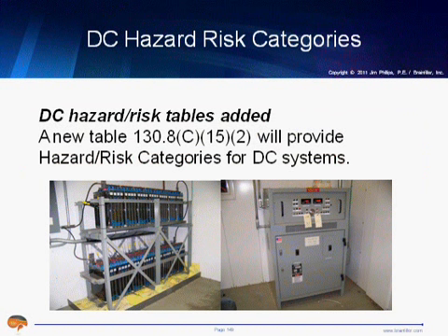With DC now being included in the 2012 edition of 70E, and for DC arc flash, we have hazard risk categories for DC as well, and these kind of parallel what we have with the AC tables. With the DC tables, you'll be looking up your voltage, and you'll be looking up the short circuit current, which is also in the table, and then you have a hazard risk category and all the other associated information that goes with this. So this is going to be a great step, because I know from my own experience, I get the question a lot, what are we going to do about DC arc flash? And so having this in the NFPA 70E, the 2012 edition, is going to be a great leap forward, and this whole thing is greatly appreciated by everybody in the industry.